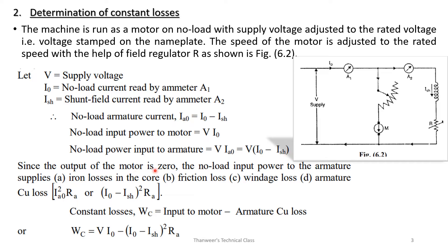Since the output of the motor is zero, the no-load input power to the armature supplies the iron losses in the core, friction losses, windage losses, and armature copper loss.